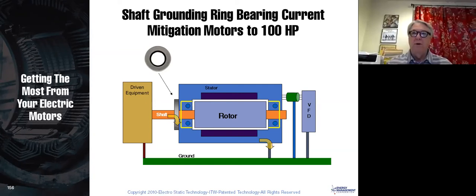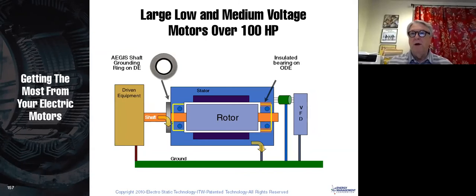If you have a motor under about 100 horsepower, you just need 1 grounding ring. And if you have a motor over 100 horsepower, they recommend that you have a grounding ring on the side of the driven equipment, and an insulated bearing on the other side, because on large motors, you can get circulating currents within the motor that will destroy your bearing. So that's straight from Aegis, the people who have the patent on this technology.